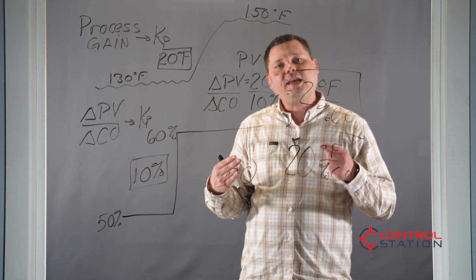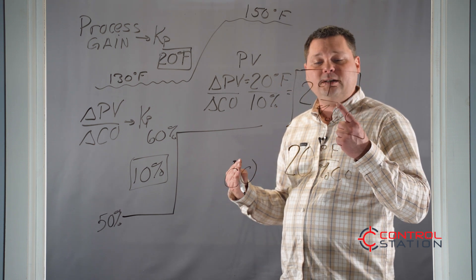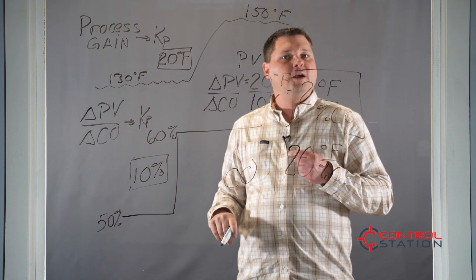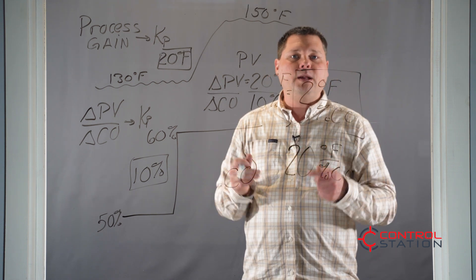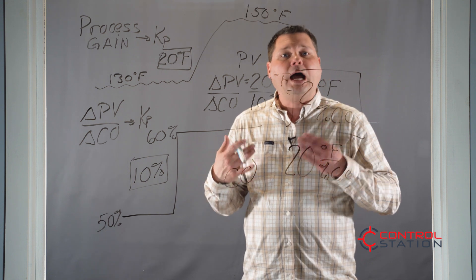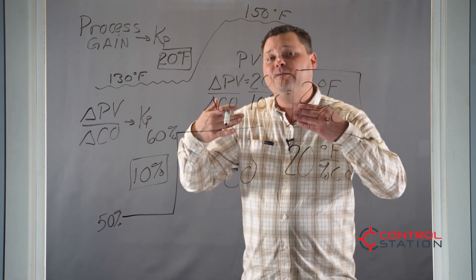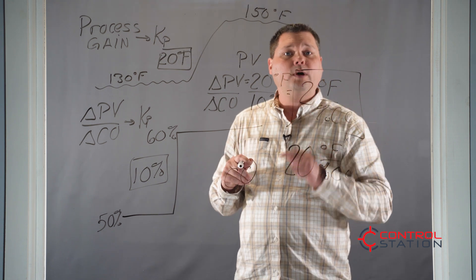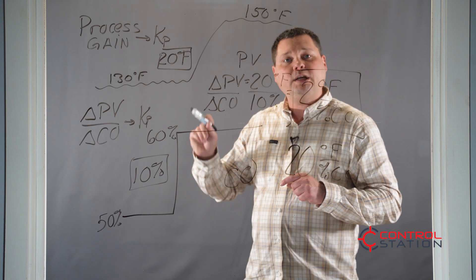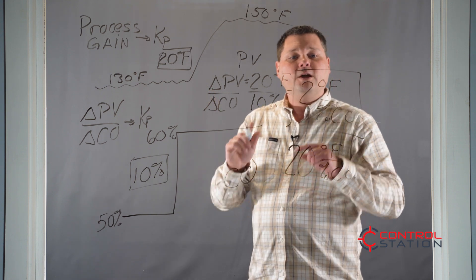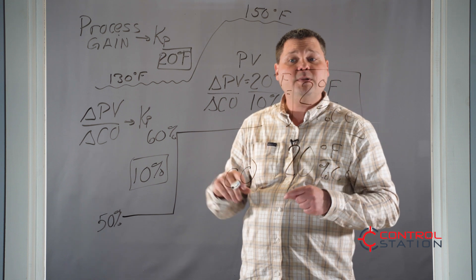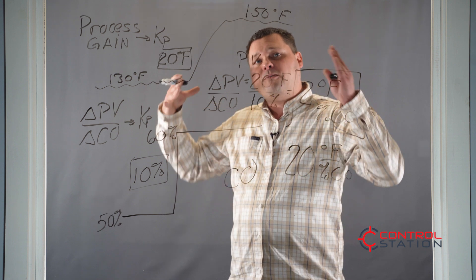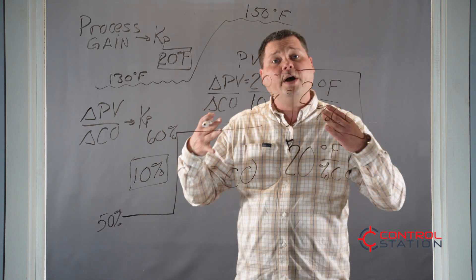Think about this: if I can move a valve accurately only 1 percent, the best control I'm going to get is probably 2 degrees Fahrenheit. So if I needed to accurately manipulate the temperature to 0.2 degrees, I would have to accurately move the valve 0.1 percent. If I cannot accurately move the valve 0.1 percent, I'm not going to achieve that 0.2 degree control. It helps us understand the controllability and sensitivity of the system, and all those things we can use to refine our control objective and understand what is possible.